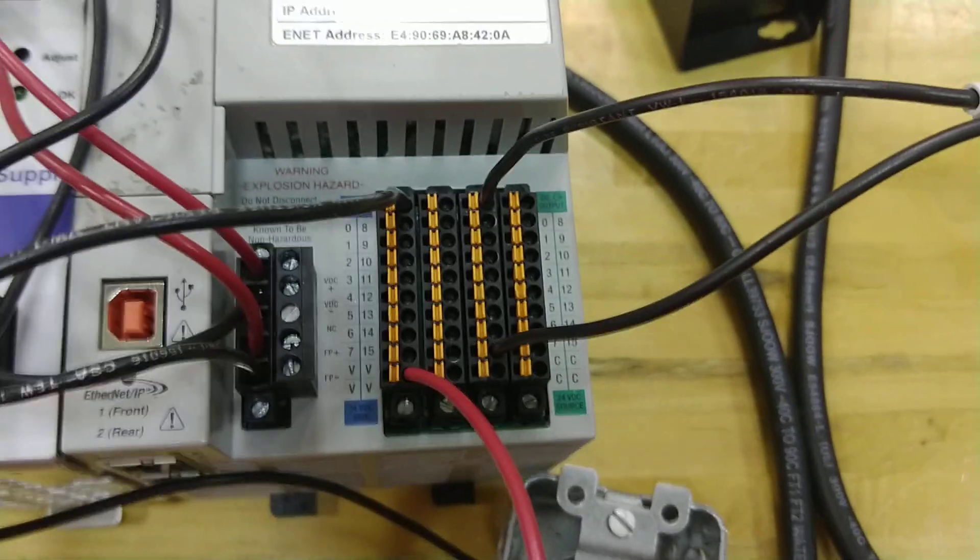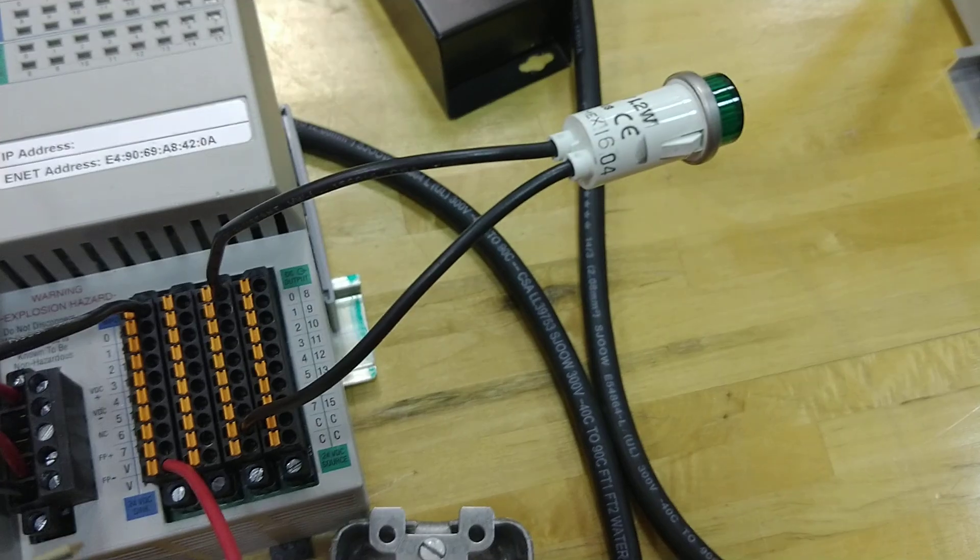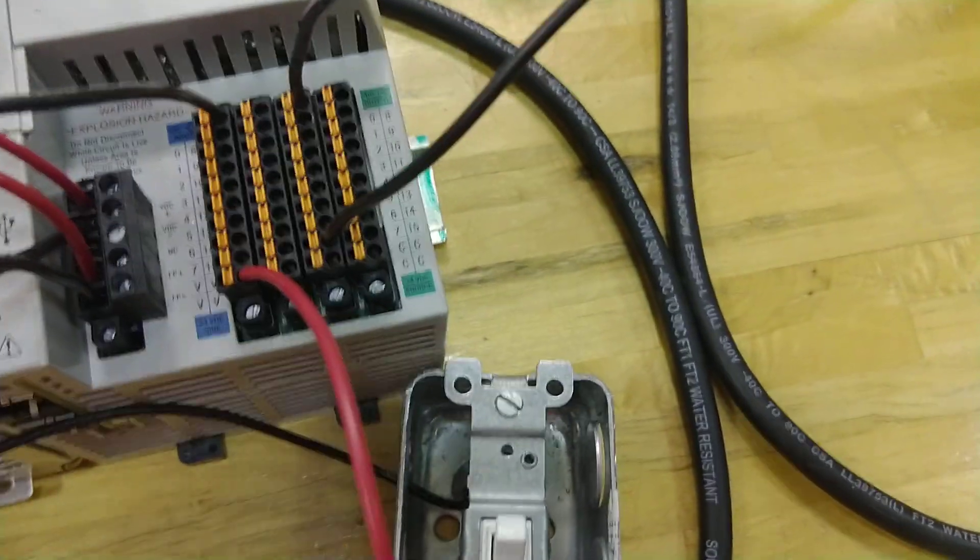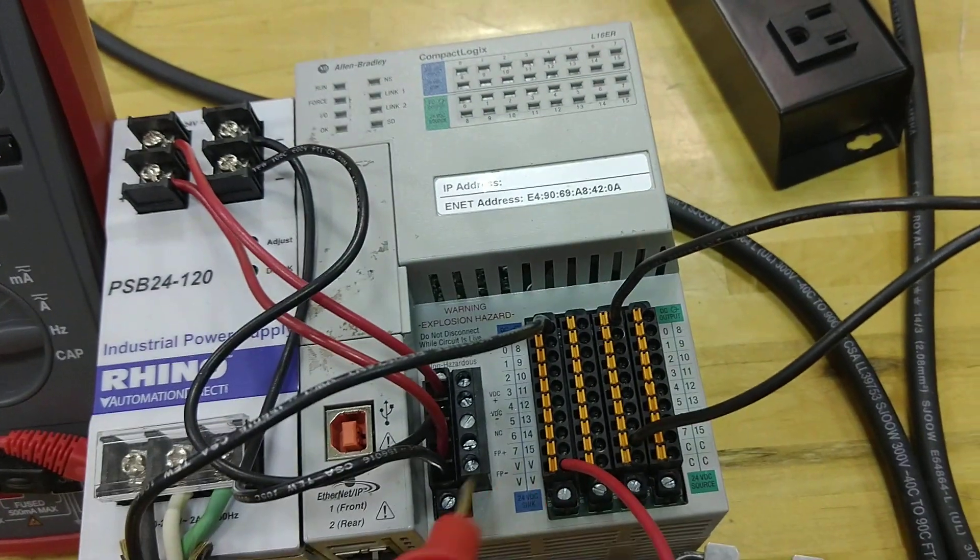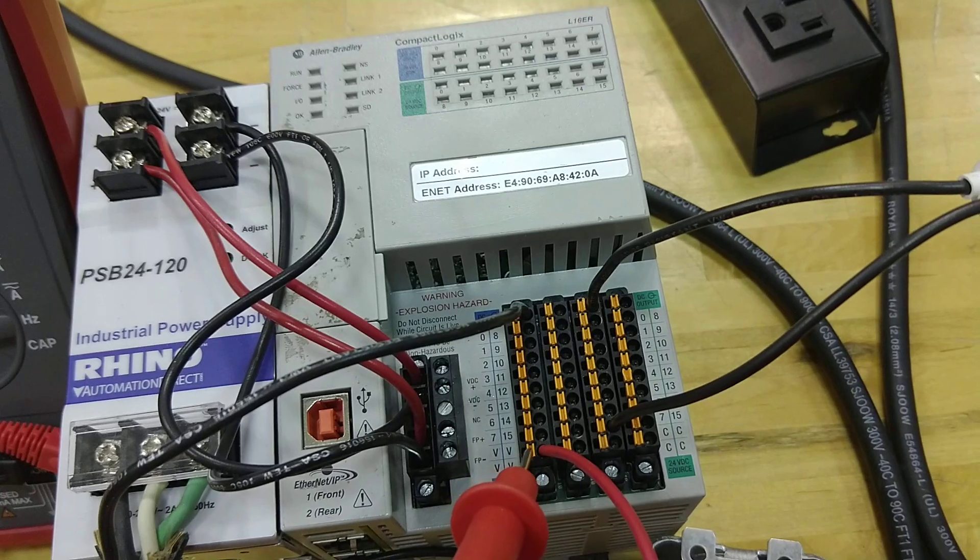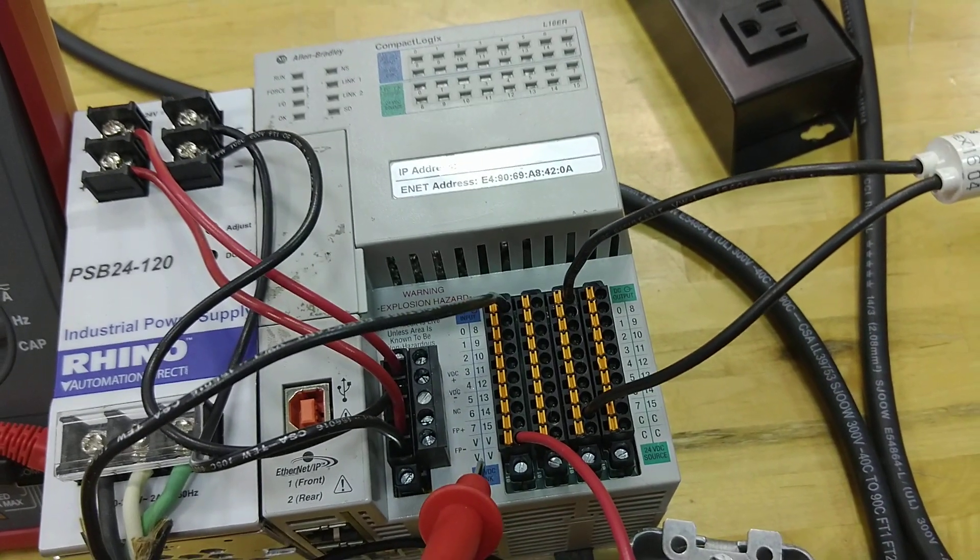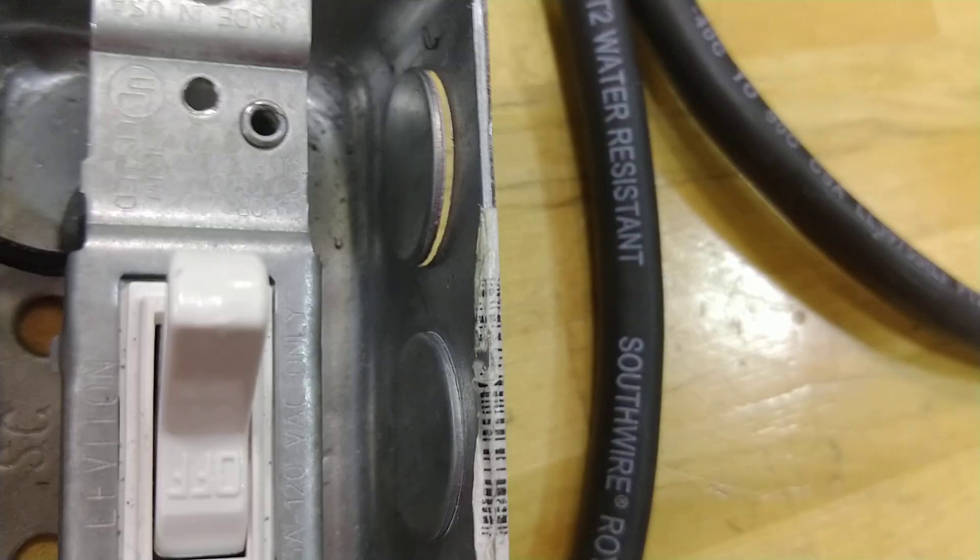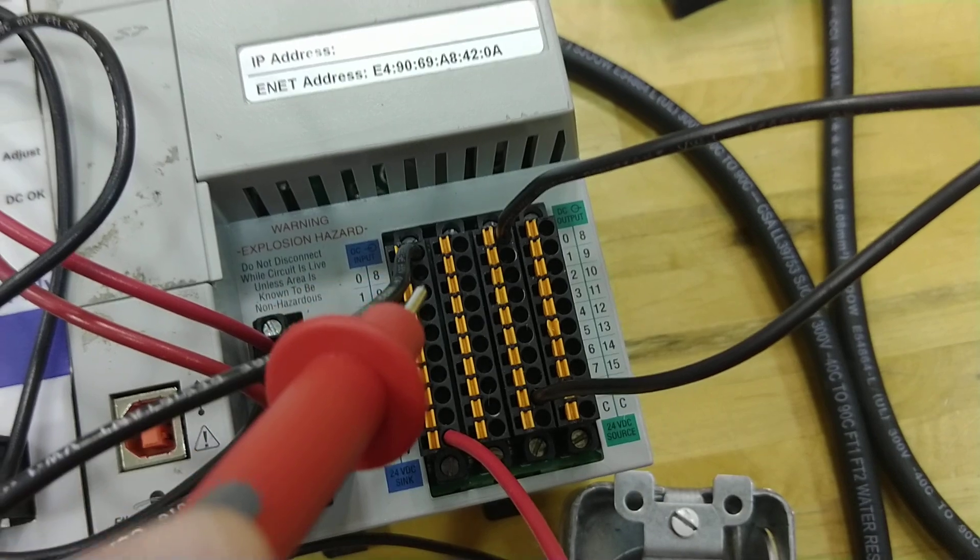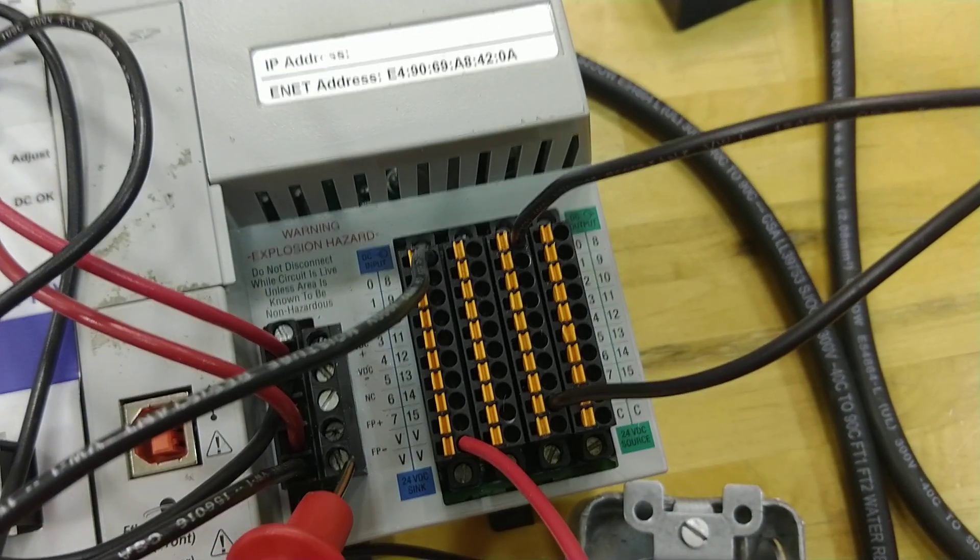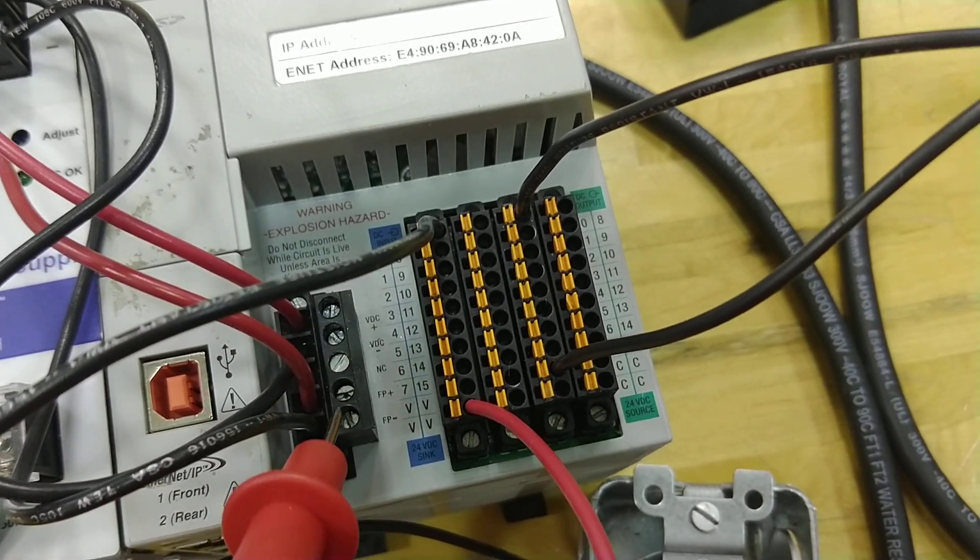And if we trace the wires of this, because I know I got a switch right here and I got a light, because I know that the power from the DC power supply, this red line is coming to this field power here. It's going to come out of this. I can tie off of it right here. It can come out of this red line through my switch. So you can see it tied to the switch back here and out that black wire to my input. Now, because I have this already set up here for this field power, it's automatically a ground from there to there.